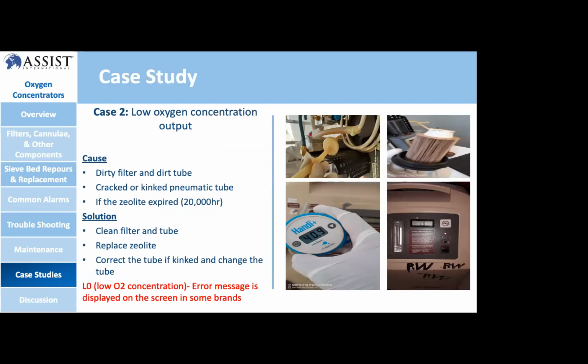In case two, we encounter low oxygen concentration output, or low oxygen concentration delivery to the patient. The causes for this problem are a dirty filter or dirty tubes, a cracked or kinked pneumatic tube or airway, and also if the zeolite is expired, the output oxygen concentration gets low. Those are the causes we identified for low oxygen concentration delivered to the patient.